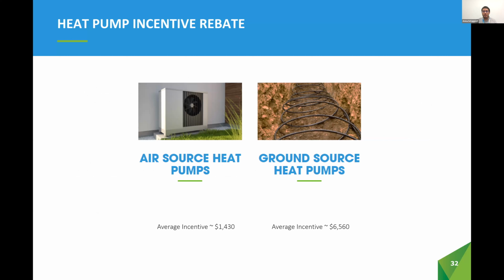Air source heat pumps have the benefit of ease of implementation, generally lower upfront cost, but have temperature operating limits which require supplemental heat. Ground source heat pumps have the highest seasonal heating efficiency and can reduce winter peak demands. When properly designed and sized, these systems are very reliable and have great longevity. However, ground source heat pumps typically have a higher upfront cost compared with other heating systems.